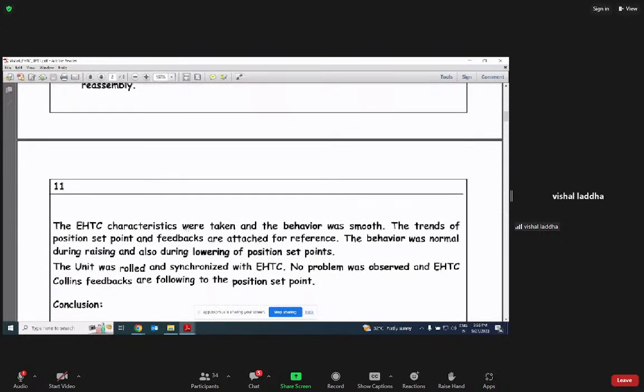The EHTC characteristics were taken and the behavior was smooth. The trends of position set point and feedback are attached for reference. The behavior was normal during raising and lowering of the set points. The unit was rolled and synchronized with EHTC. No problem was found on EHTC.